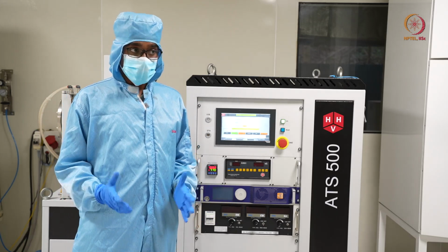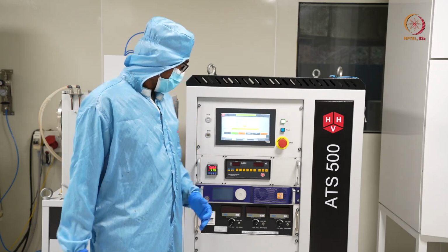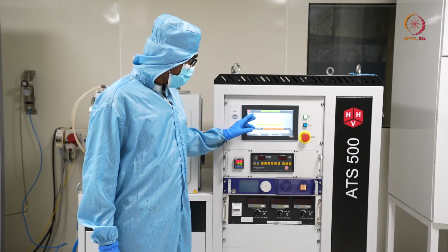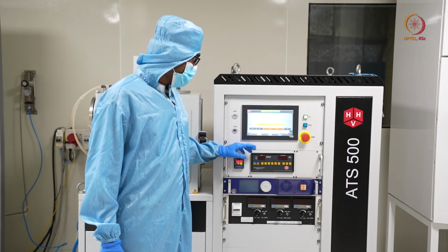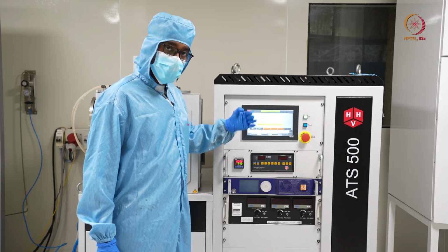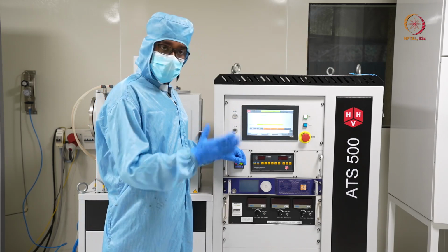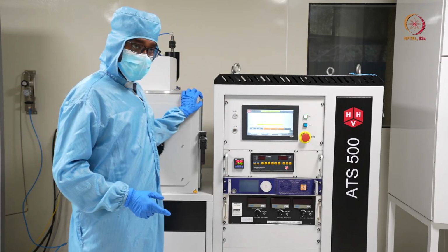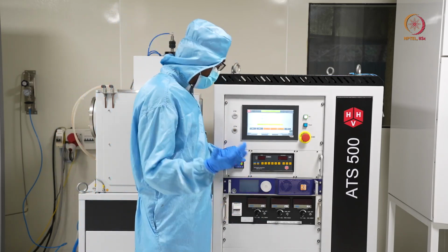So till that much we will wait, because after that something else is also there to discuss. As you can see here, we left it for quite a long time, and it is already in the e power minus 5 range. You can see it will reach around 7.5 e power minus 5, and it is still decreasing. At this stage we can turn off the tool. We have to wait till this much, otherwise enough vacuum will not be there, so efficiency will be lost day by day. It will take a long time, but it's a kind of deterioration process.